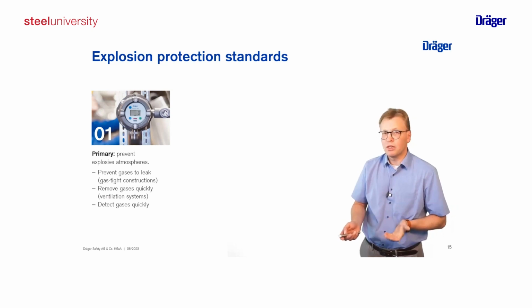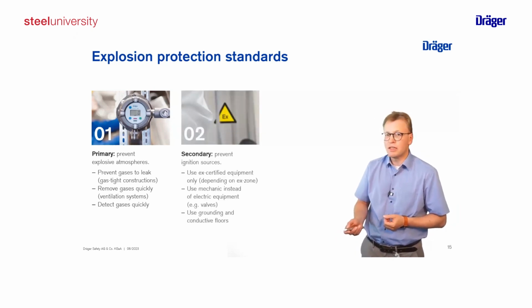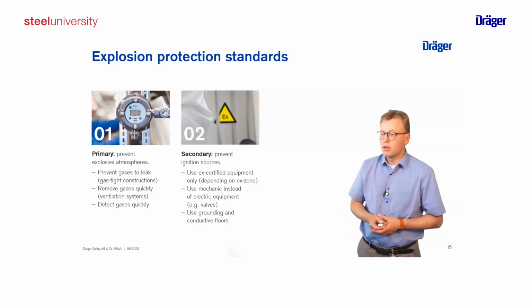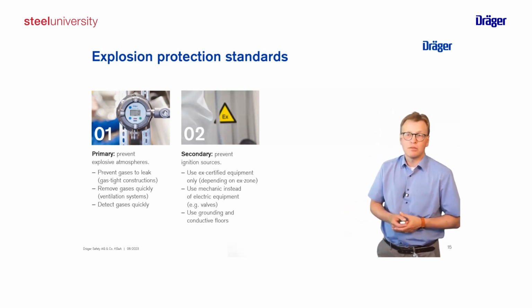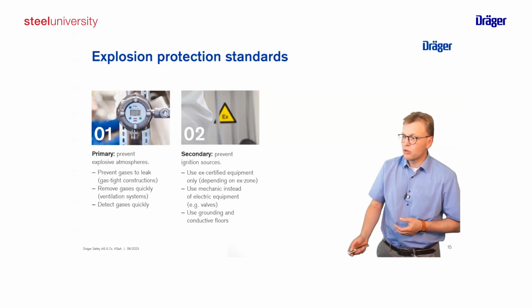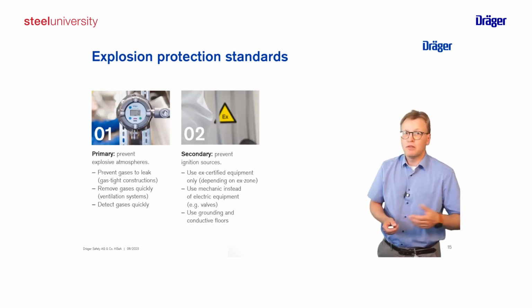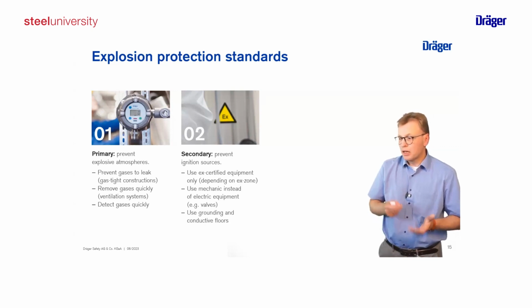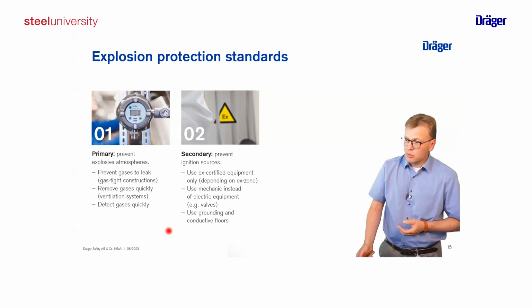The second, if we can't avoid this because it's part of the process that explosive atmosphere could be present, then at least we have to prevent ignition sources from being present. So equipment which could ignite our explosive atmosphere. And for this, we use Ex-certified equipment only. So when we have identified the probability of an explosive atmosphere and have defined the requirements for the equipment, we can select the right equipment which can be used there. And as well, we have to ensure that electrical installation, grounding, etc. is done properly.